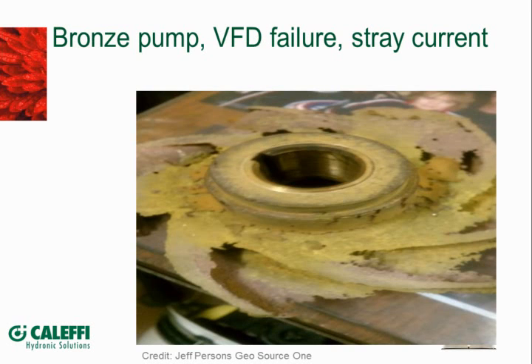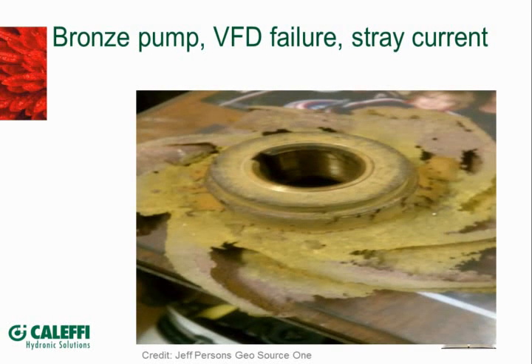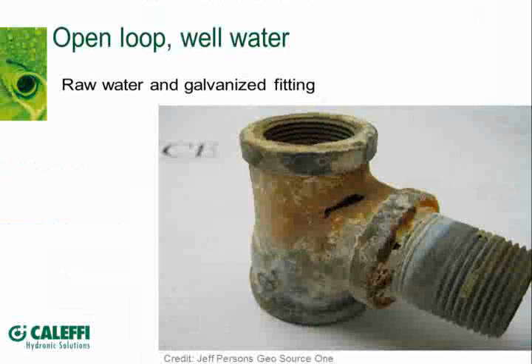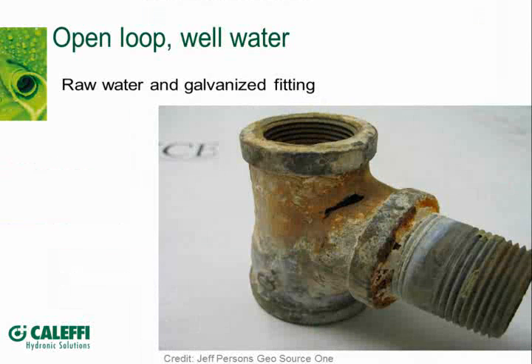And it shows almost complete, I want to say electrolysis, depletion on the impeller of this pump. It would be something to watch out for and make certain that there's good grounding for things. And if you do experience problems with motors and drives, that you're watching for stray electrical currents.